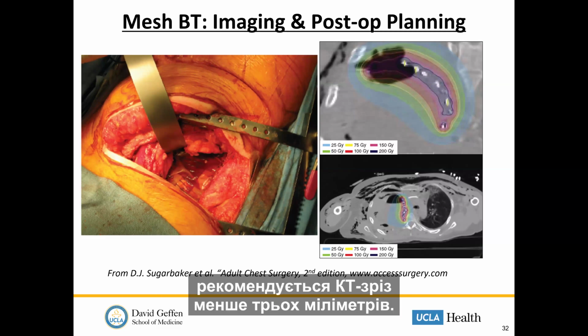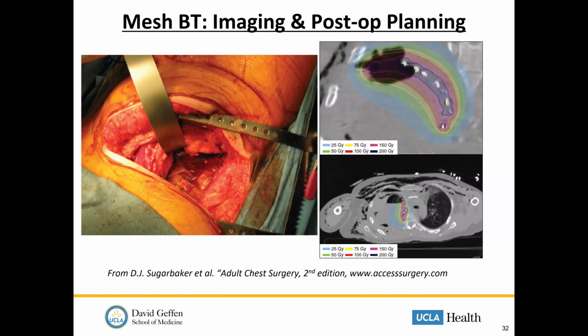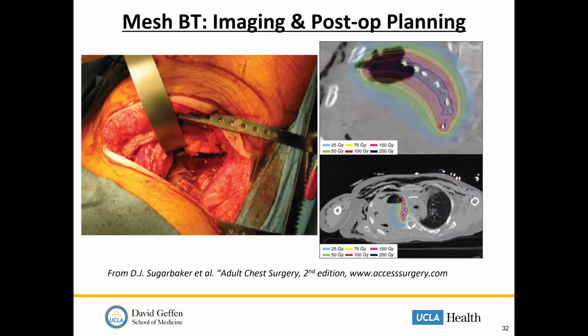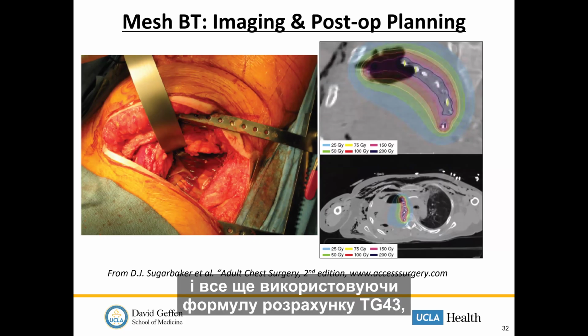One month after, the patient comes back to the hospital for the post-implant CT scan, with less than 3 millimeter CT slice recommended. Then we put this CT image into the planning system and detect each seed. Since we know how many seeds were implanted, we still use the TG43 calculation formula and calculate the dose distribution around the target area.